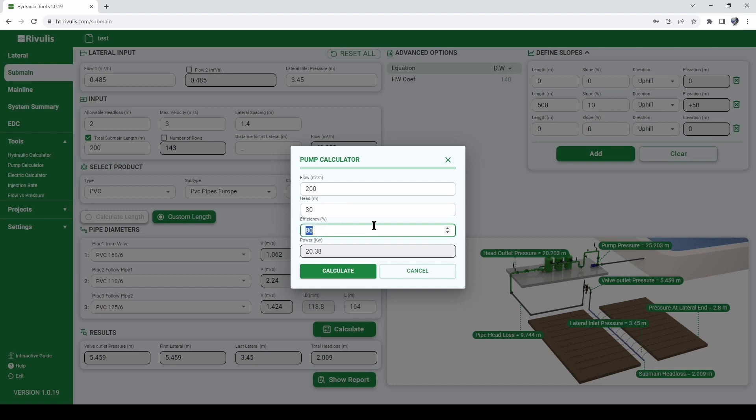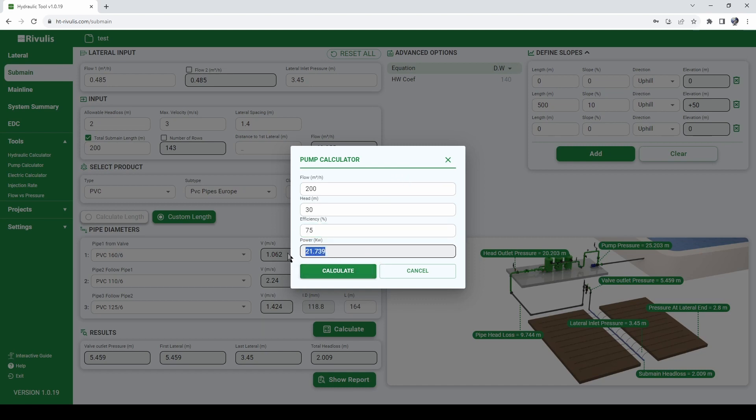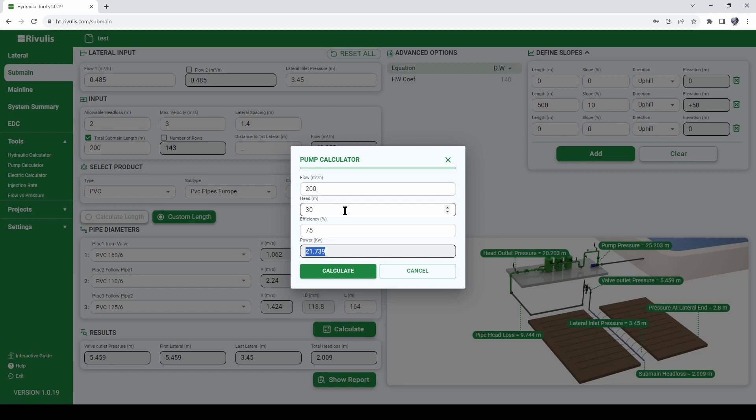And normally a pump efficiency will stand between 75-85%. Let's say 75% efficiency of the pump. We hit calculate and the calculator tells us that we will need a pump of 21.7 kilowatts. So this is the power of the pump required in order to pump 200 cubic meter per hour at 30 meters head.